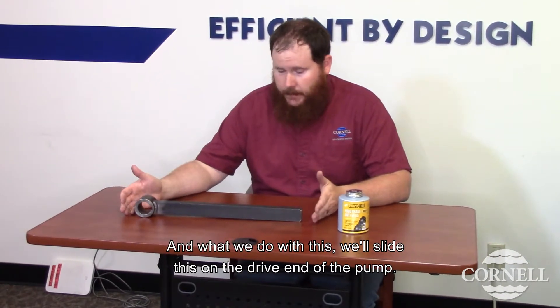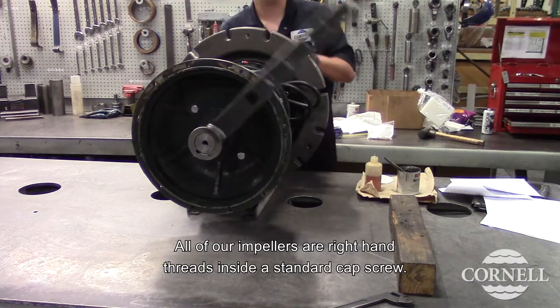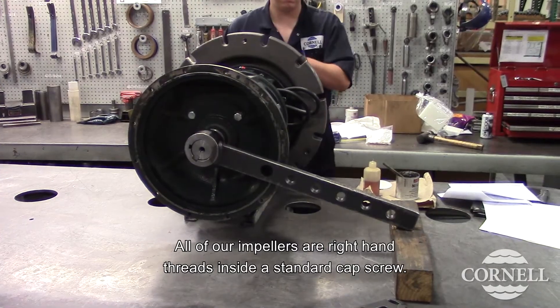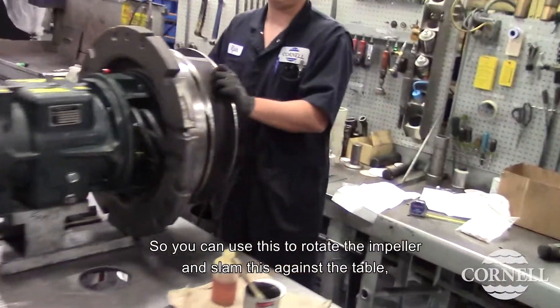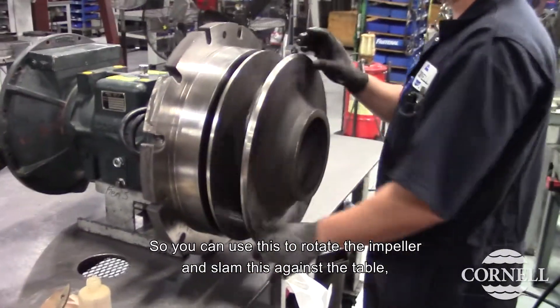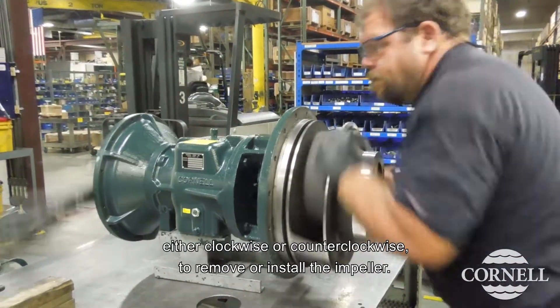What we do with this, we'll slide this on the drive end of the pump. All of our impellers are right-hand threads inside a standard cap screw. So you can use this, rotate the impeller, and slam this against the table either clockwise or counterclockwise to remove or install the impeller.